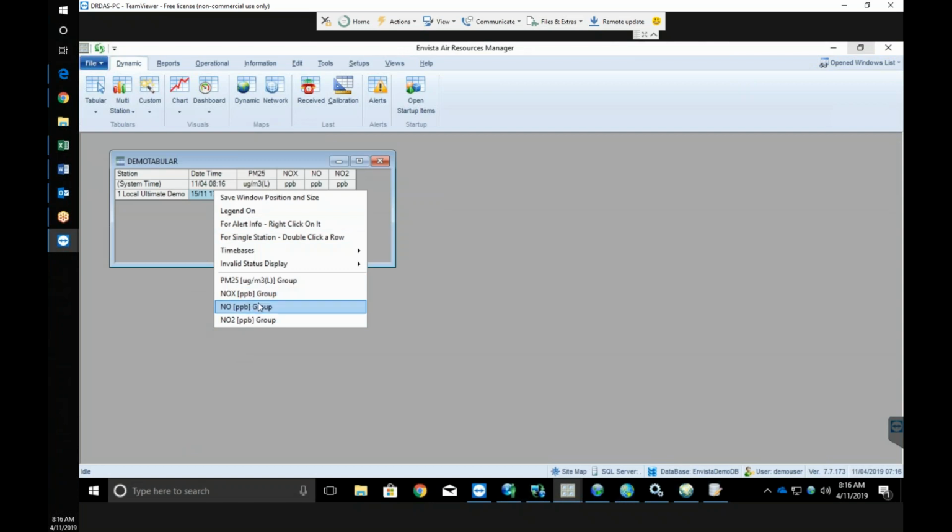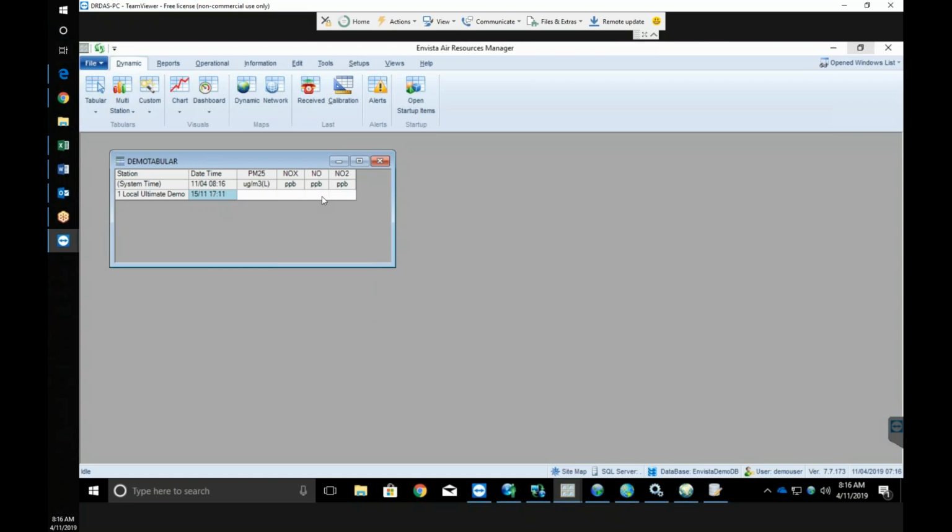That you could right-click on it and view charts from all of the NO2 in a network. Of course, here we only have the one, so it doesn't do much. When you have a value here, if you right-click, you're able to see the calibration records, the zero span checks, the diagnostics, the digital monitors, those digital alarms from the instrumentation. There's lots of features within the dynamic table that you can pull in for each relevant.